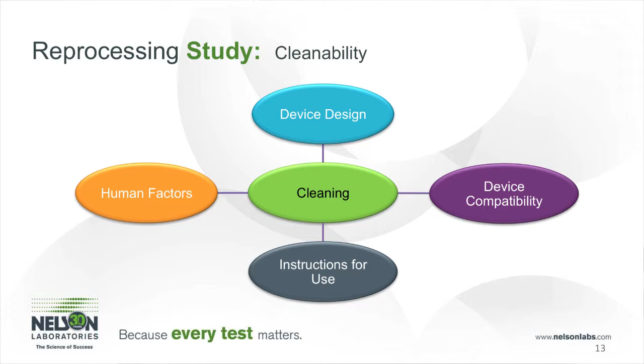So the first thing to think about is cleanability. When you look at cleanability, you look at the device design, the instructions for use, the compatibility of the device with the detergents, processes, etc., and also the human factors involved. So we want to make sure that the cleaning instructions are easy to follow for the healthcare facility as it goes into the next steps of the process.